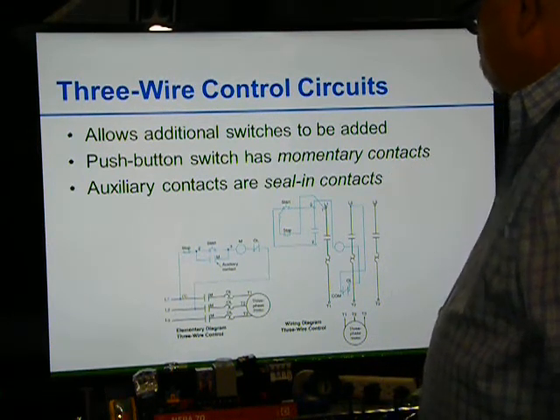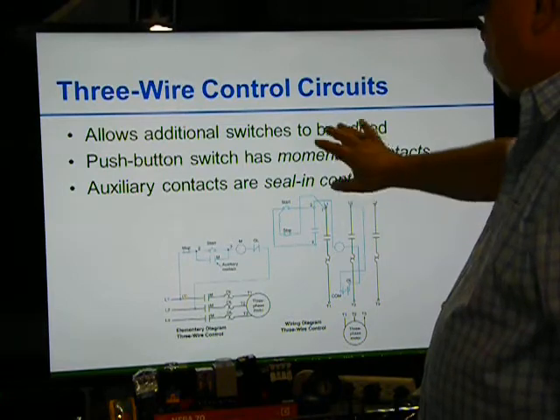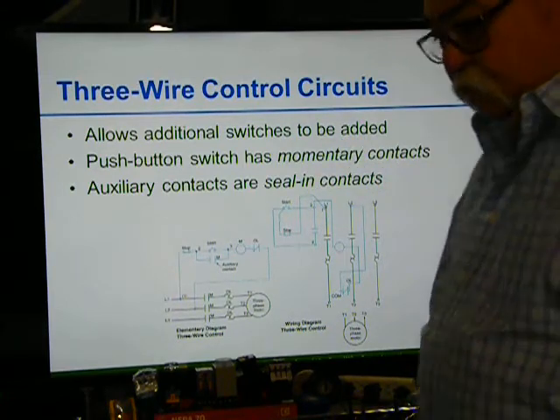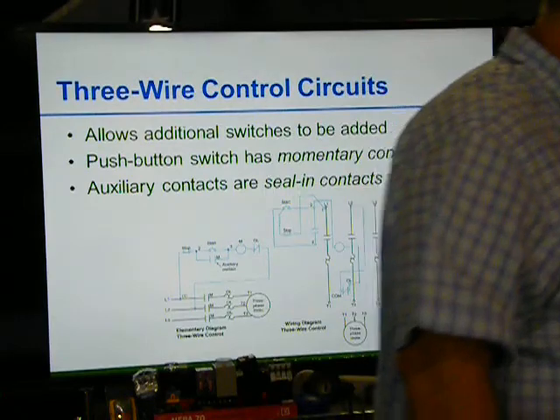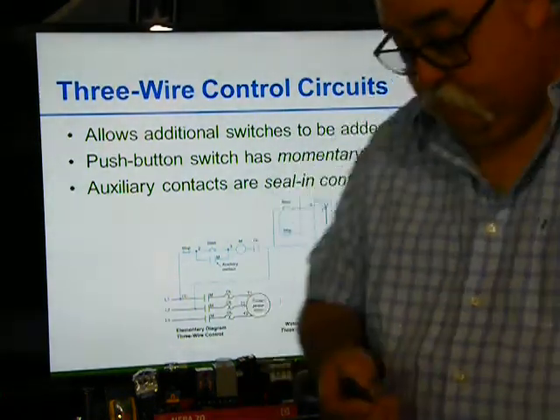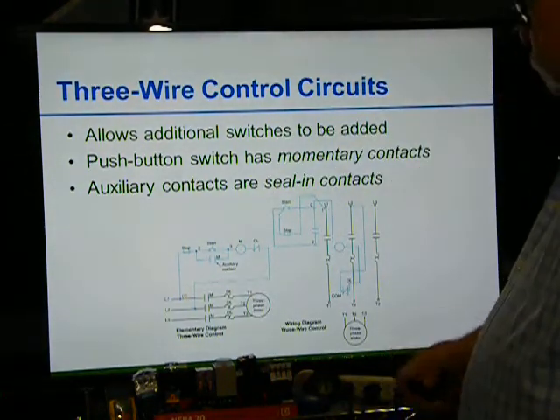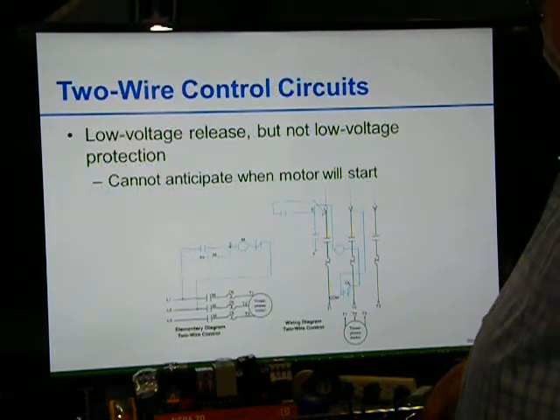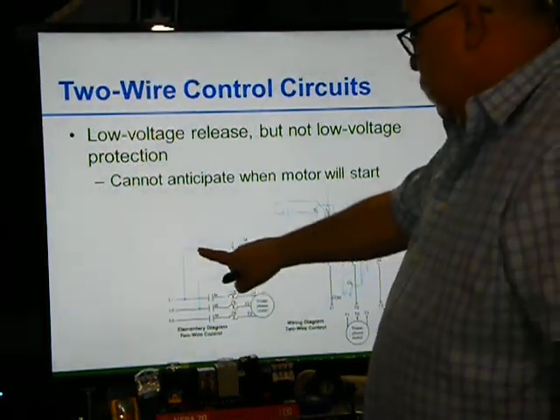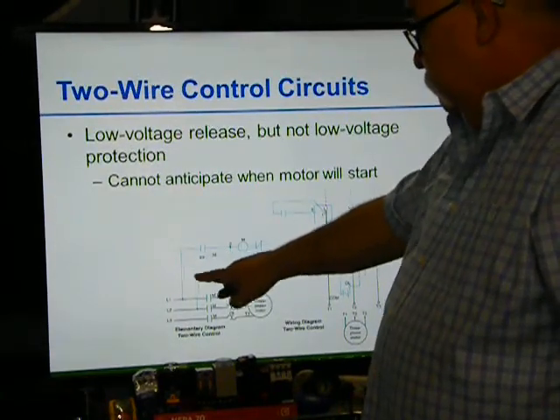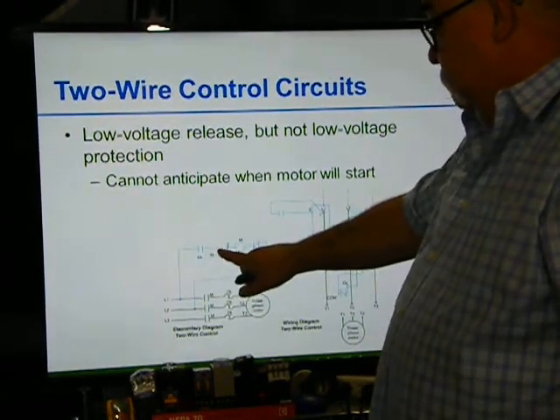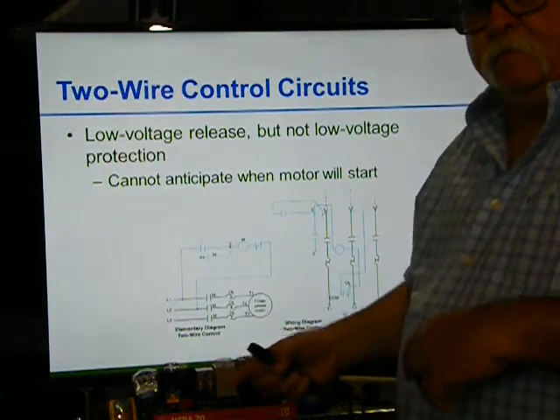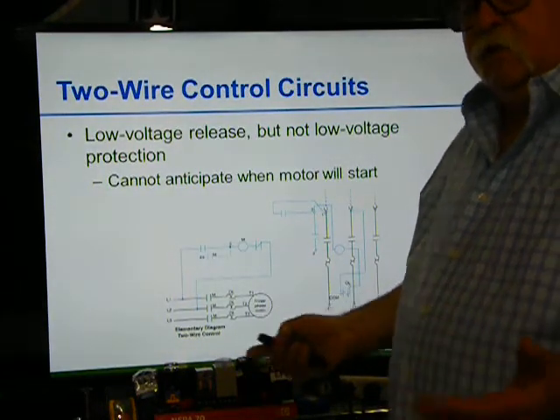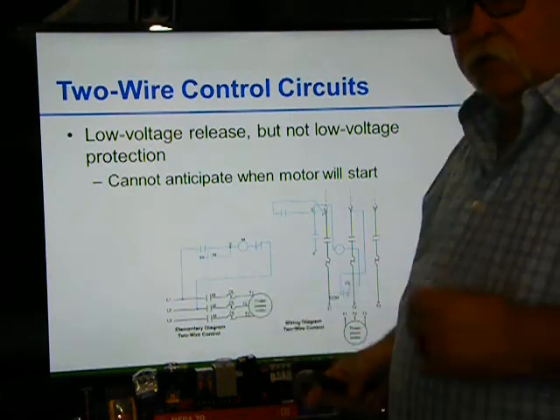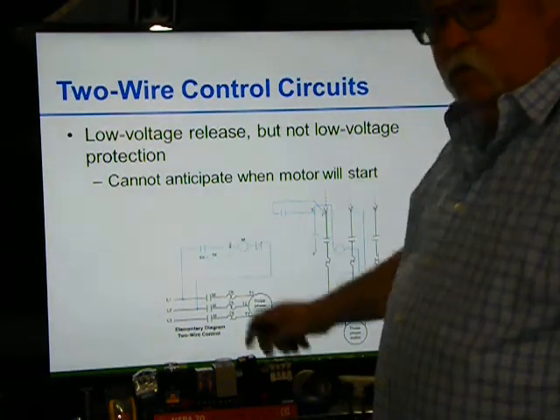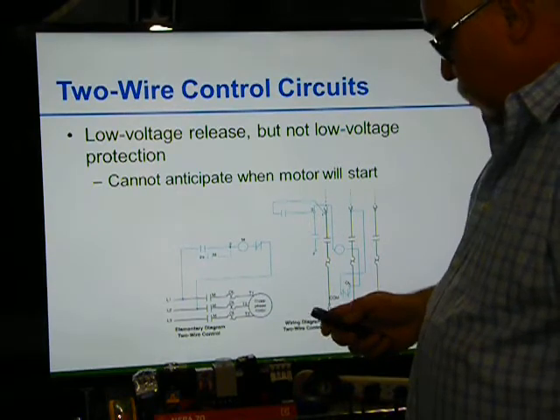Push button switches have momentary contacts. And the 3-wire allows you to add more switches compared to a 2-wire. The 2-wire, if I had another switch here, well, the thing is I have to close both of them. So if I put 2 switches in series, it doesn't do me any good. So that's the problem with this 2-wire. You only have one means to open and close it.